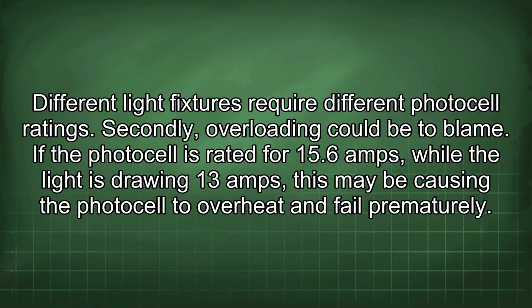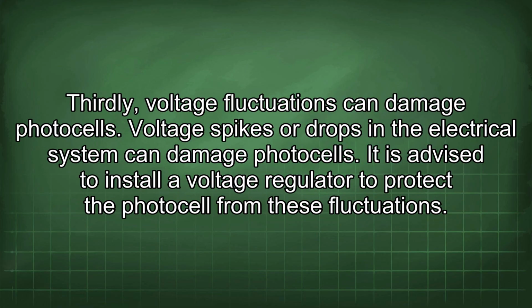Secondly, overloading could be to blame. If the photocell is rated for 15.6 amps, while the light is drawing 13 amps, this may be causing the photocell to overheat and fail prematurely. Thirdly, voltage fluctuations can damage photocells. Voltage spikes or drops in the electrical system can damage photocells. It is advised to install a voltage regulator to protect the photocell from these fluctuations.